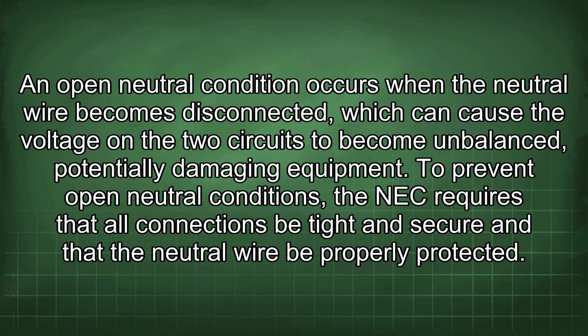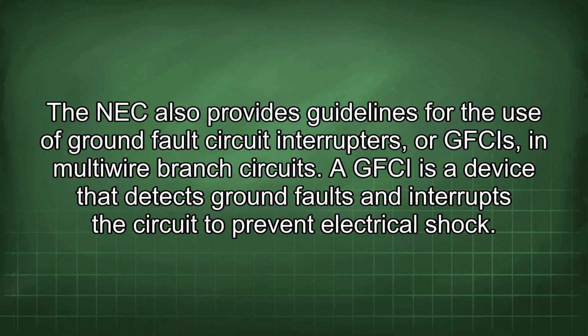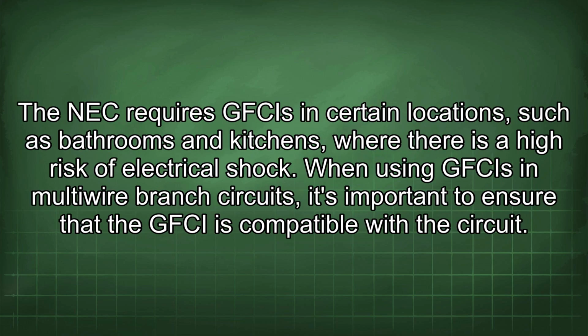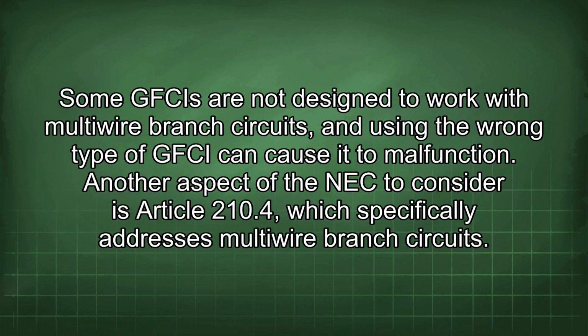To prevent open neutral conditions, the NEC requires that all connections be tight and secure and that the neutral wire be properly protected. The NEC also provides guidelines for the use of ground fault circuit interrupters, or GFCIs, in multi-wire branch circuits. A GFCI is a device that detects ground faults and interrupts the circuit to prevent electrical shock. The NEC requires GFCIs in certain locations such as bathrooms and kitchens where there is a high risk of electrical shock. When using GFCIs in multi-wire branch circuits, it's important to ensure that the GFCI is compatible with the circuit. Some GFCIs are not designed to work with multi-wire branch circuits, and using the wrong type of GFCI can cause it to malfunction.